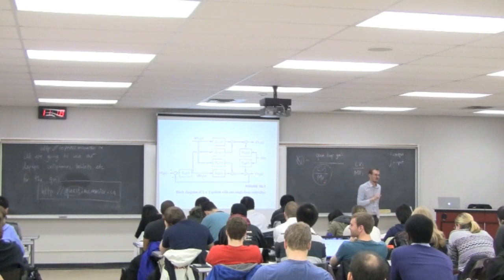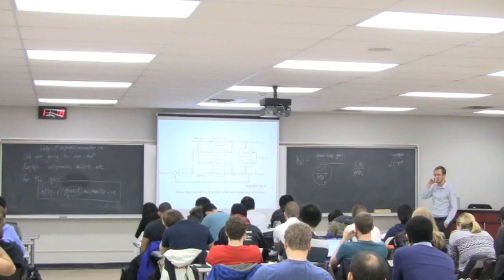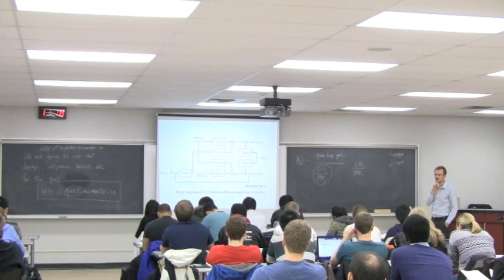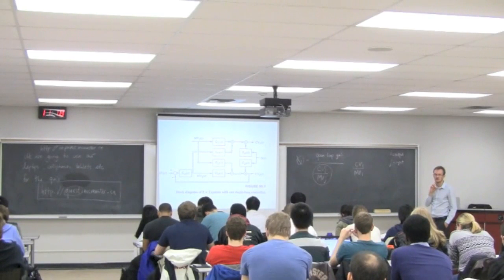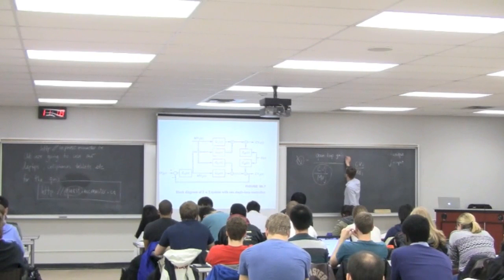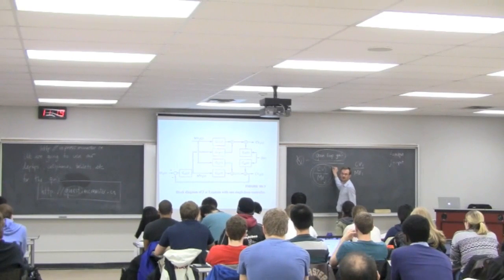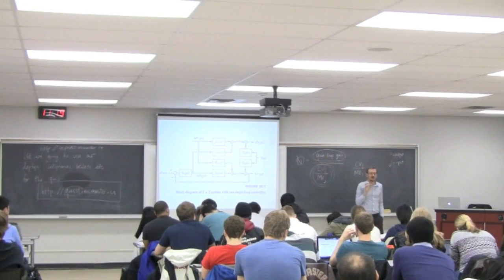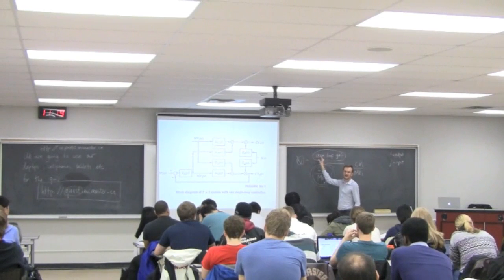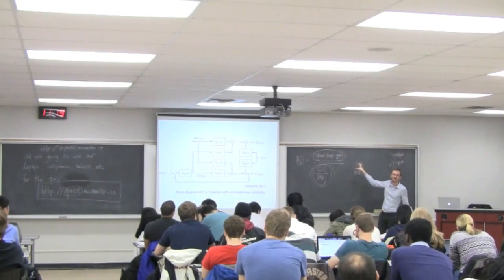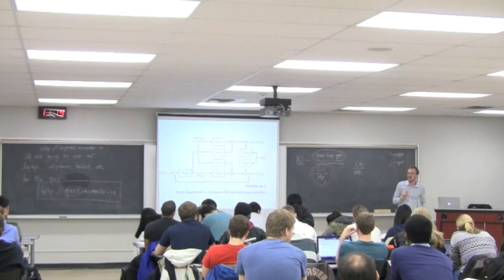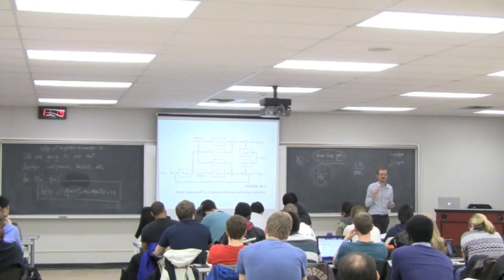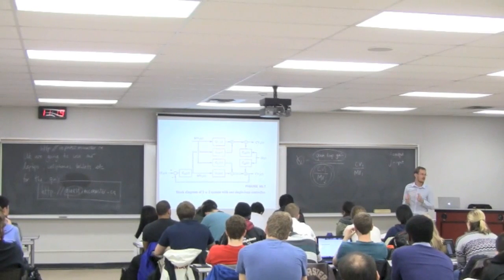Now what about negative lambdas? What if lambda ij was negative? What is that telling me? It's telling me my open loop gain has a different sign to my closed loop gain. Maybe the open loop gain is positive, the denominator is negative, so I get a negative lambda ij, or vice versa. It still tells you there's a cause and effect relationship between i and j, but you're playing a dangerous game when you're pairing on a negative. The reason is that the gain in the open loop case is different when you're in closed loop. It's telling you your system's sign of behavior changes when you've got the loops closed versus the loops open.